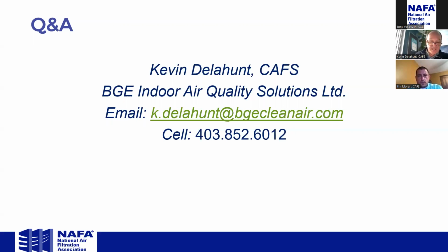And third is design flexibility. One thing that I've been commenting on in new air handling unit design is adding an extra filter bank. It might sound weird, but just picture a rooftop unit that has an empty bank that you would implement during, for us, wildfire smoke season. 7 of the last 10 summers and springs, we've had a tremendous amount of particulate generated from forest fires right across Western Canada. But it would also serve during a pandemic.